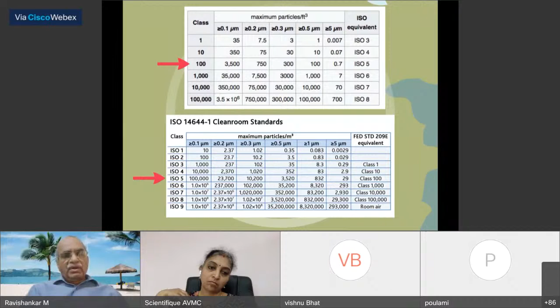I told you about the HEPA filters. The HEPA filters are positioned right on top, so that there's no obstruction to the airflow, excepting the lighting system that is fixed in the center, and a little bit of arm movement here and there, but predominantly the flow is likely to be straight. The cooled air is pressurized on top of these filters because they have a very high resistance, and then it flows down from the top towards the patient.